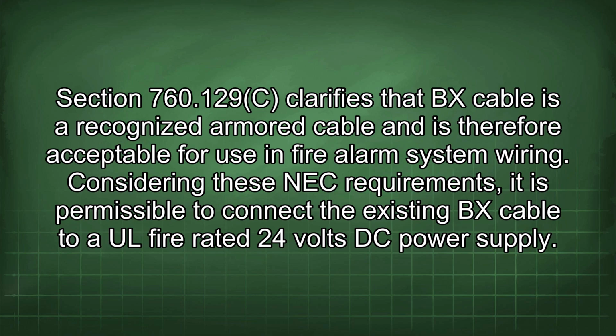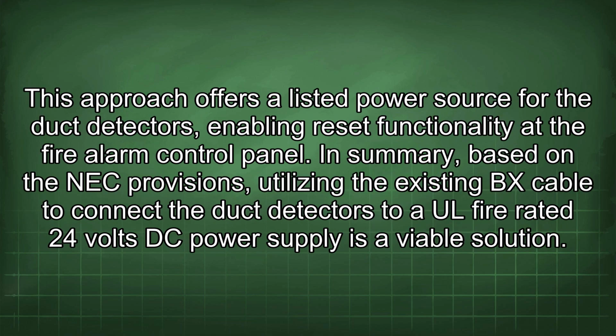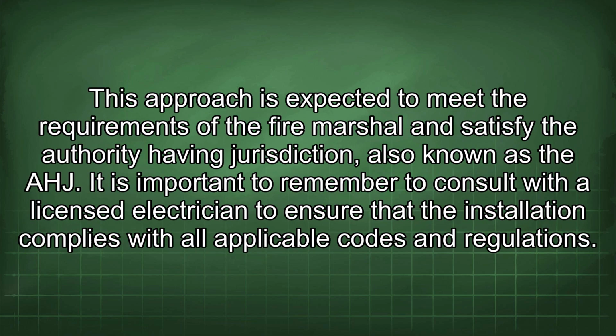Considering these NEC requirements, it is permissible to connect the existing BX cable to a UL fire-rated 24 volts DC power supply. This approach offers a listed power source for the duct detectors, enabling reset functionality at the fire alarm control panel. In summary, based on the NEC provisions, utilizing the existing BX cable to connect the duct detectors to a UL fire-rated 24 volts DC power supply is a viable solution. This approach is expected to meet the requirements of the fire marshal and satisfy the authority having jurisdiction, also known as the AHJ. It is important to remember to consult with a licensed electrician to ensure that the installation complies with all applicable codes and regulations.